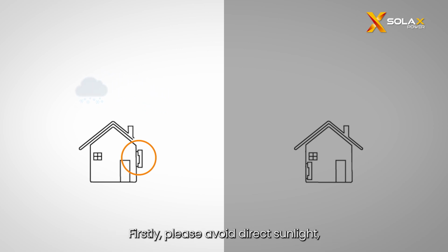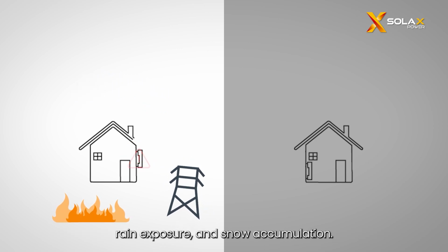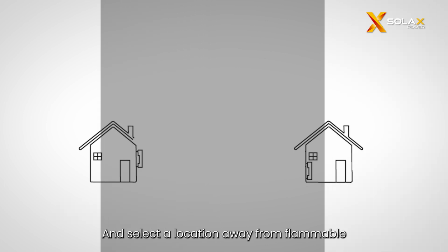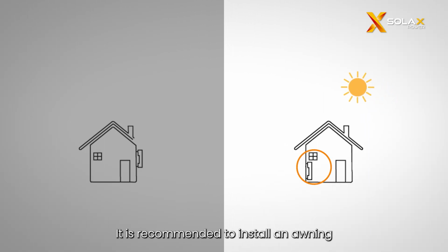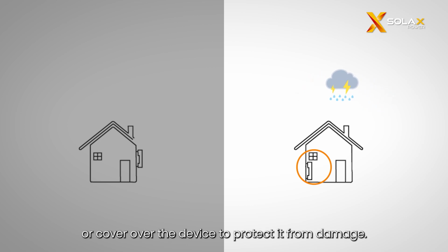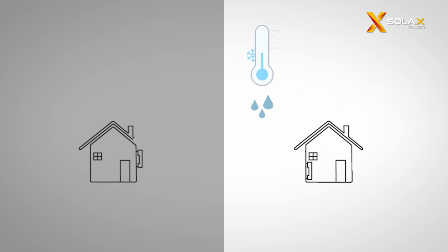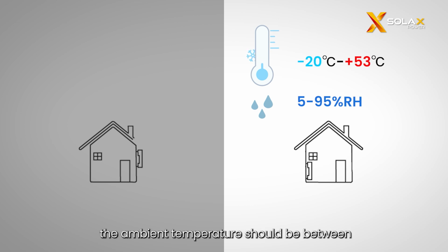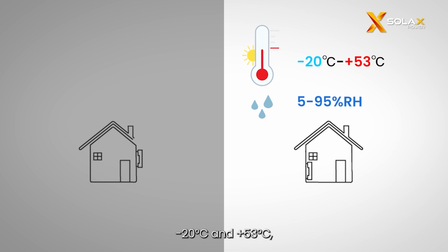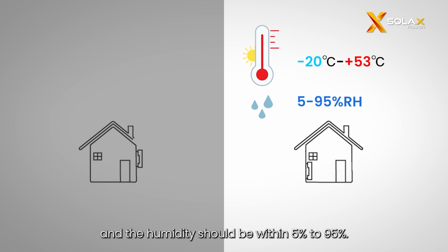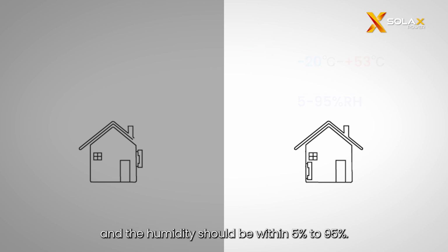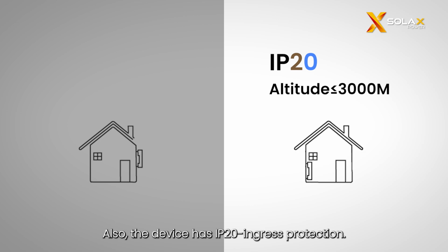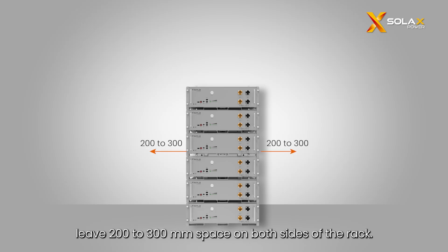Firstly, please avoid direct sunlight, rain exposure, and snow accumulation, and select a location away from flammable materials and antennas. It is recommended to install an awning or cover over the device to protect it from damage. Secondly, the ambient temperature should be between -20 degrees Celsius and +53 degrees Celsius, and the humidity should be within 5% to 95%. Also, the device has IP20 ingress protection. Remember to avoid installing the device at altitudes exceeding 3,000 meters. In the case of rack mounting, leave 200 to 300 mm space on both sides of the rack.